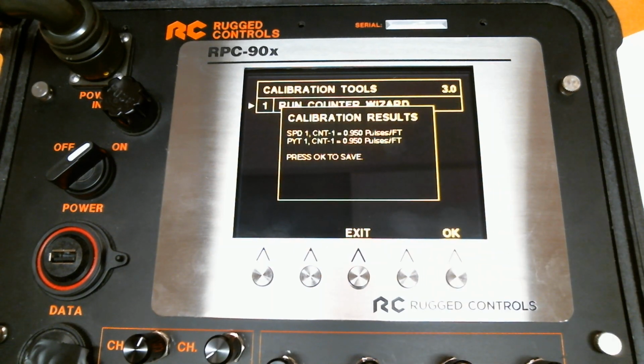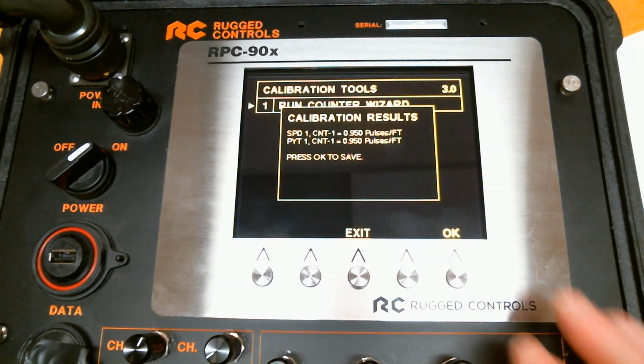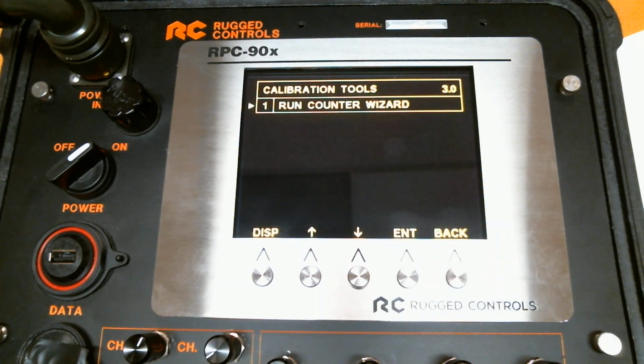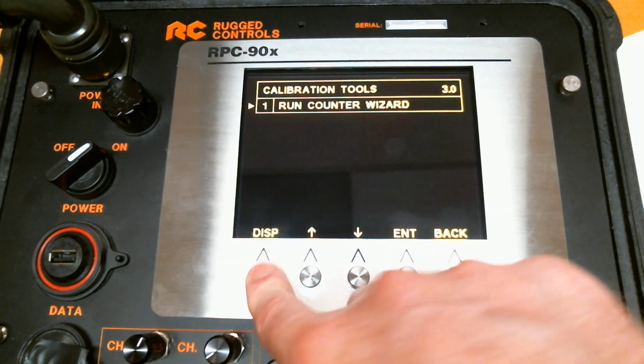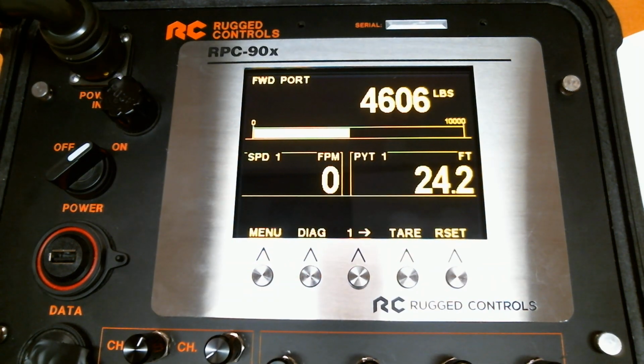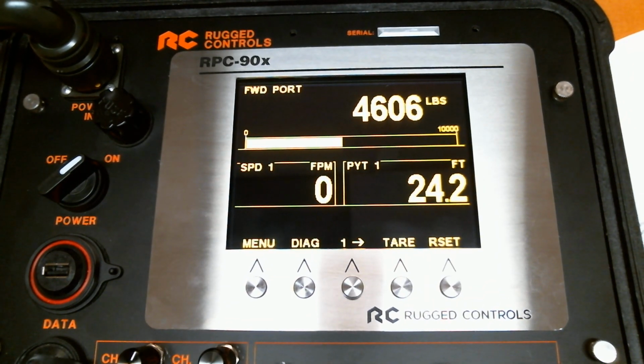And now both the speed and payout are live calibrated, and we are okay to save the values, and we can go back to display. We would want to probably check it by running it back and forth a few times. You might need to do it a couple times to dial it in exactly, but this interface will get you where you need to go.